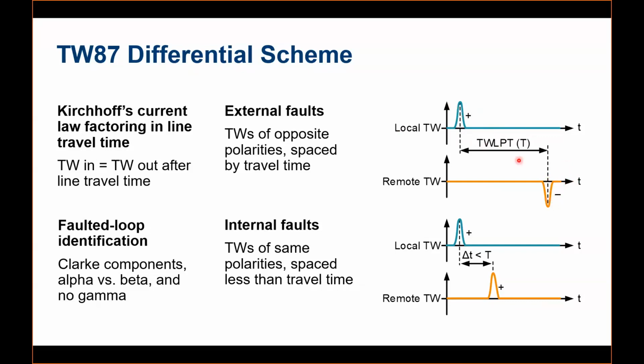And one more important thing is the duration or the time reference between these two traveling waves. The capture time will be separated by the line propagation delay, which we have measured before. So a traveling wave will enter and it will leave the remote end after this time. So if we have these two things in place, opposite polarities plus the peaks separated by the line propagation delay, it is a clear indication that the fault is external. We do have some current supervision as well, but the basic principle to detect any kind of external fault is this criteria.